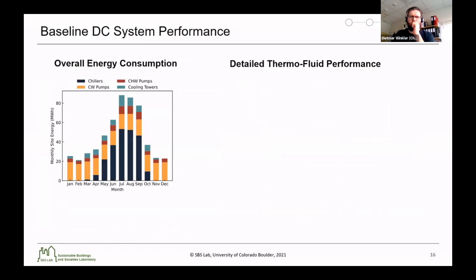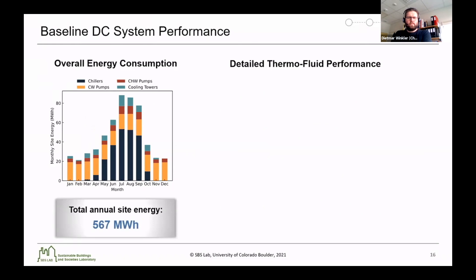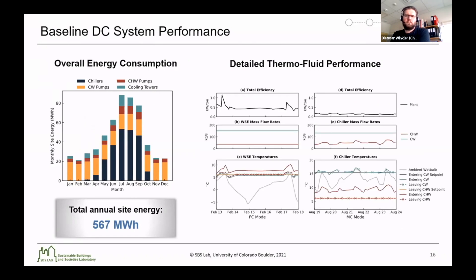For the baseline district cooling system results, in the summer the plant consumed the most energy, though there were still some cooling needs in the colder months as well. In summer, most of the energy was consumed by the chillers, while in other seasons the condenser water pumps were the dominating factor. On an annual basis, this site consumed 567 megawatt hours. We also looked at the detailed thermofluid performance for both free cooling and mechanical cooling modes. We noted that the condenser water mass flow rate in free cooling in particular was fairly high, and relative to the ambient wet bulb temperature there was space to increase the delta T on the condenser side, which would improve cooling tower efficiency while also reducing pump energy consumption.